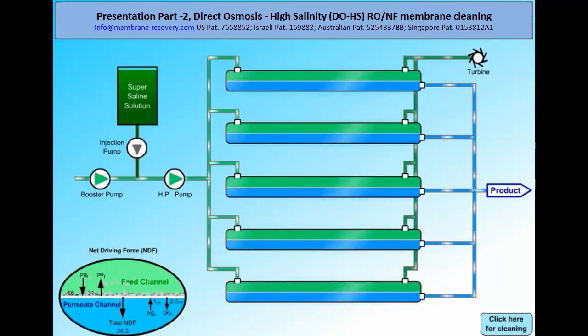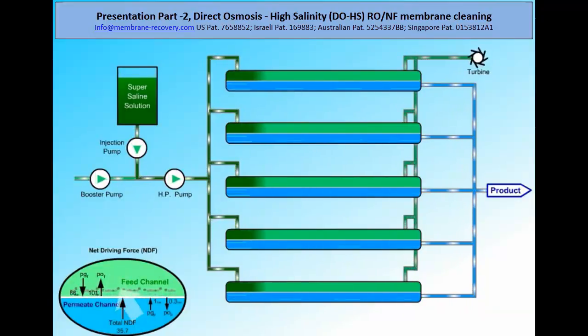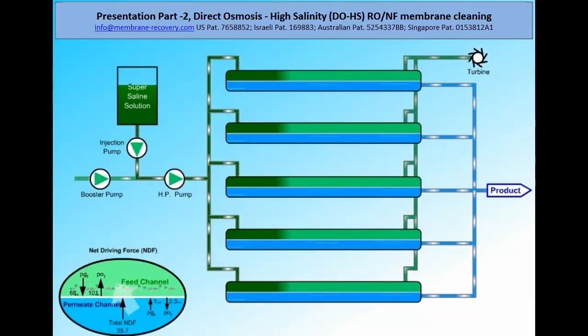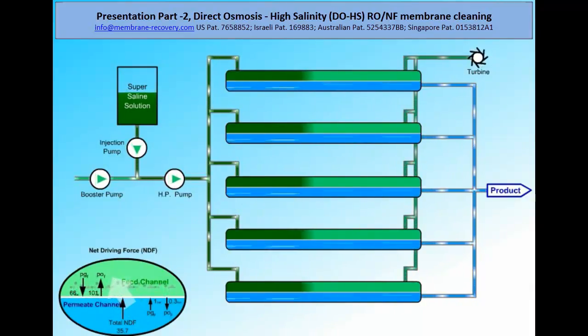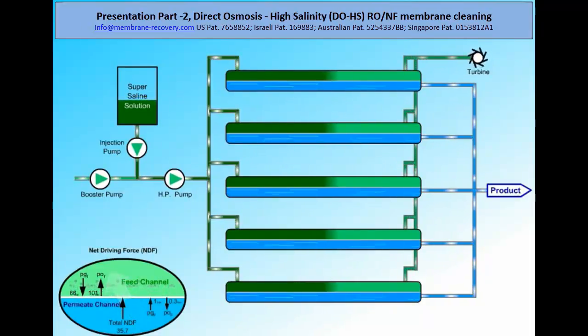Let's start with the direct osmosis cleaning. When the pump and RO train are in normal operation, a few gallons of concentrated table salt are injected into the suction side of a high-pressure pump. 30 seconds is the maximum injection time used for seawater application. For brackish water, it'll be between 5 to 15 seconds only.